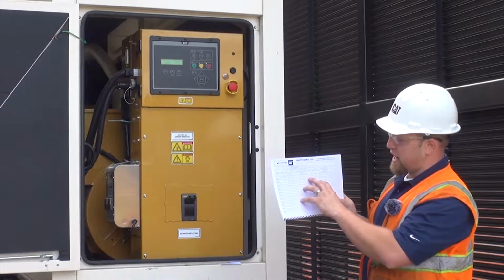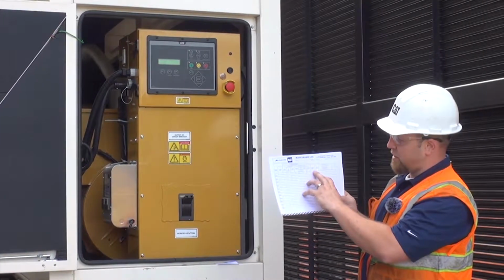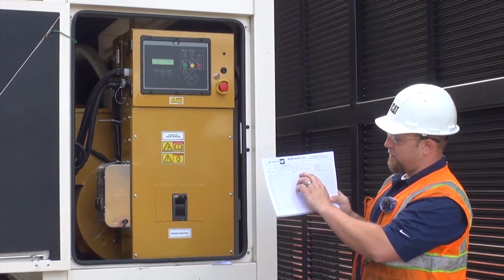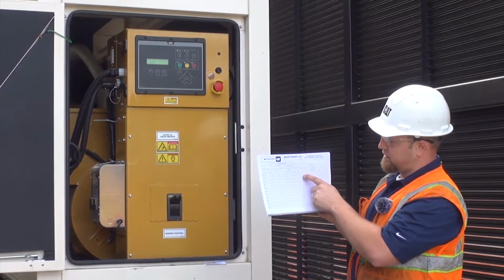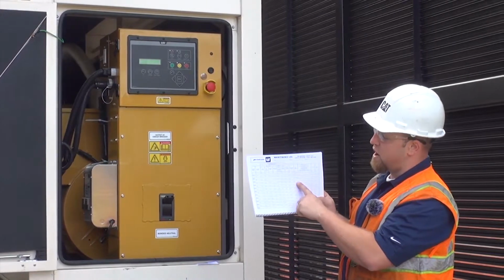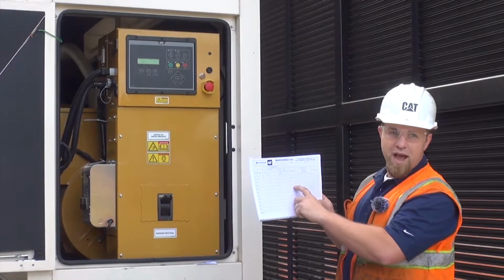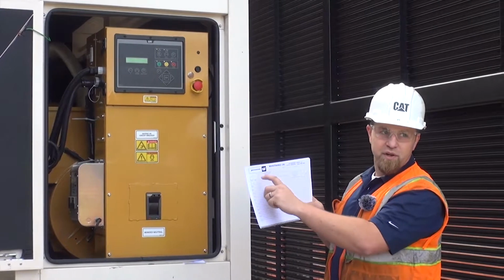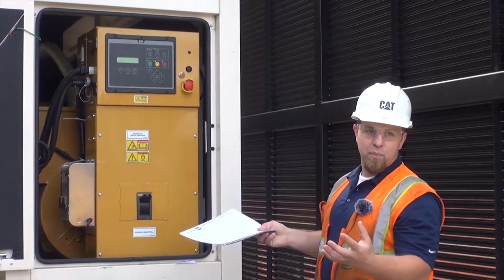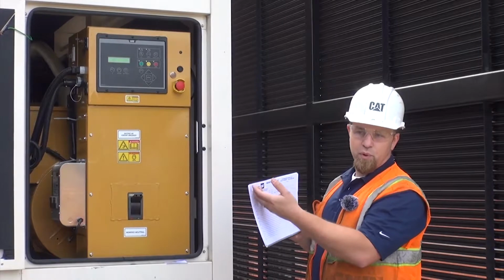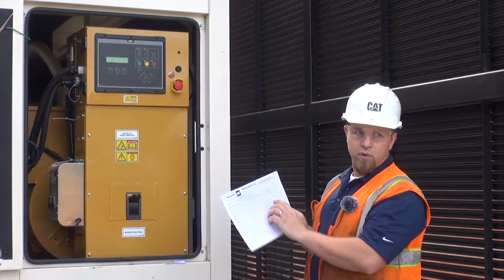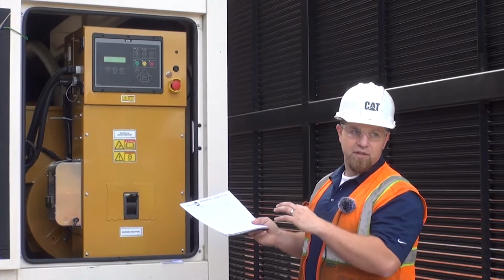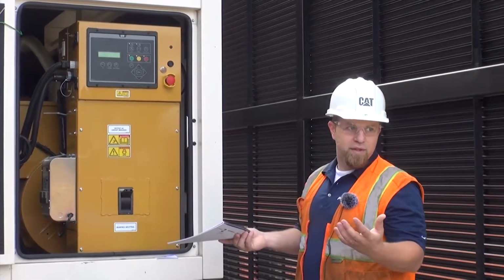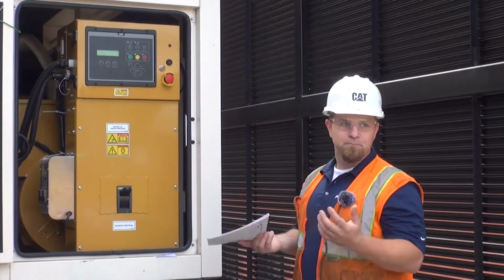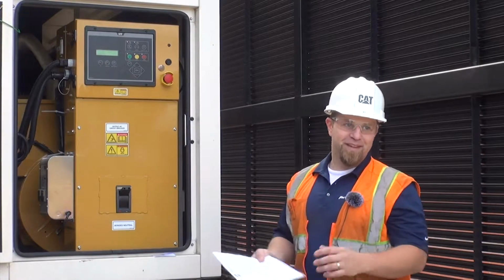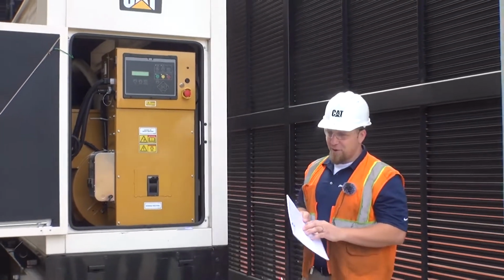The other portion where they'll catch you on that is AC voltage and frequency. You'll have that every week, so it'll be 0 amps, 0 amps, 0 amps. Once a month you'll do a building transfer, you'll have amps on there. So they'll be able to see your runtime and your amps. That proves that you've done your weeklies. It proves that you've done your building transfer and that you recorded how much load is actually on it. Those are the things that they really want to see. If they get nitpicky, sorry, you got a bad fire marshal. You know, I've seen worse, I've seen better.